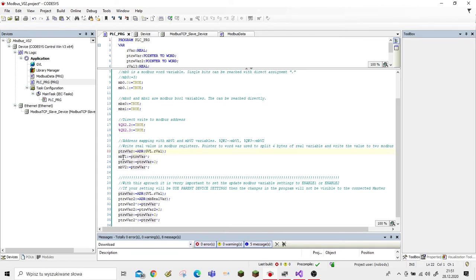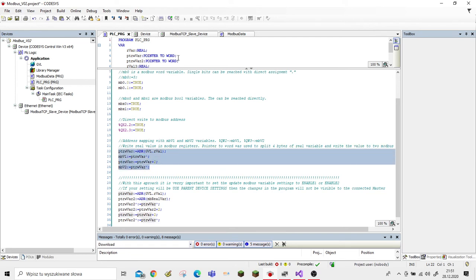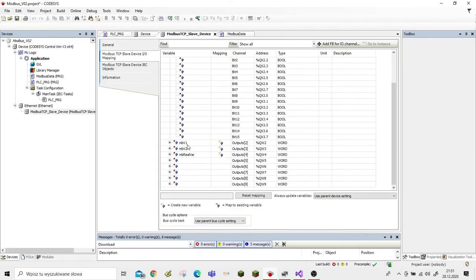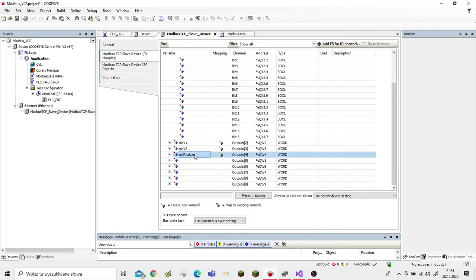Then we write to our Modbus register mbv1 the first two bytes. We then increment our pointer by two to jump to the second two bytes of the REAL value and assign those bytes to a second Modbus register. So the REAL value will be written into those two variables.